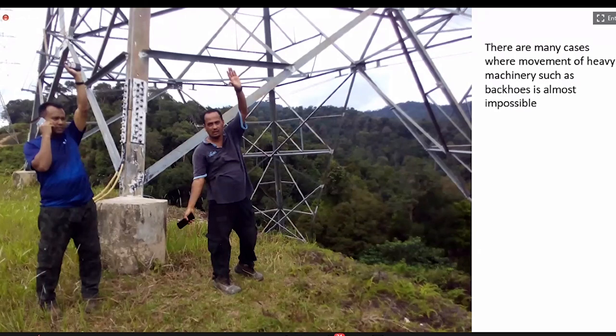So for that, you need to give a state of the art solution looking at the tower. One advice I can give you, if you are a tower constructor or an earthing provider to transmission towers: never give a quotation without having a good inspection. You visit the site, have a very good inspection, measure the soil resistivity at various places, and make a very, very careful estimation of the cost that will be incurred, not for the earthing material alone, but for the labor and installation cost.